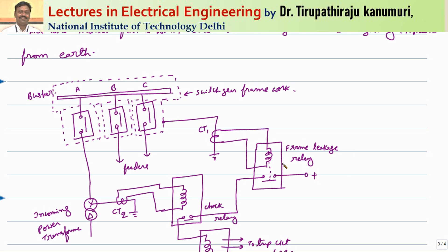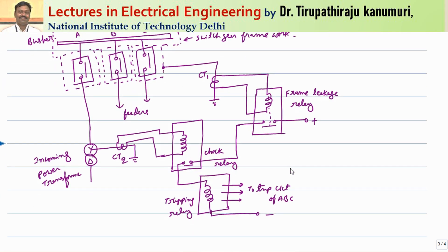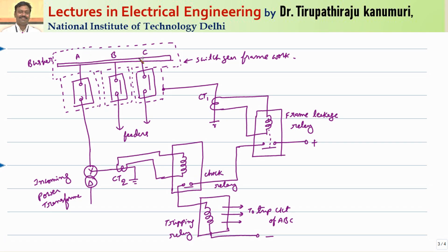To avoid mal-operation due to small transients or external faults, one more CT is connected at the star point of the incoming transformer, which operates a check relay. Only if both your frame leakage relay and the check relay operate will the tripping relay activate and trip all the circuit breakers. Let us take different cases to analyze this.